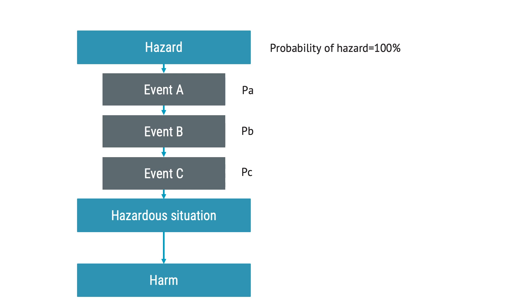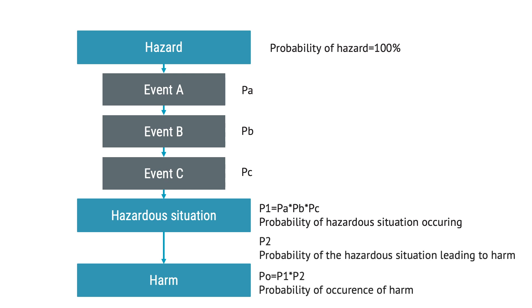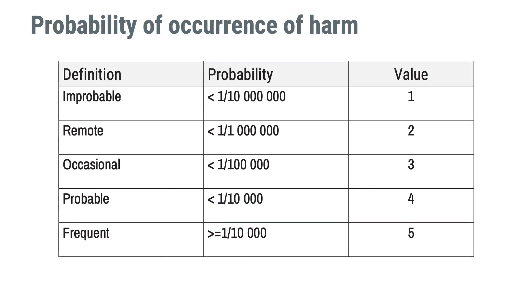These events all need to occur in sequence in order for the hazardous situation to arise. In this case, P1 equals pA times pB times pC. And in order to get to P0 — the probability of occurrence of harm — we need to factor in P2, the probability of the hazardous situation leading to harm, which in the previous example was extremely low. Finally, P0 equals P1 times P2, where P1 is the result of the previous sequences or combinations of events and their respective likelihoods. When you have figured out the probability of occurrence of harm, you can find the right number in your probability of occurrence of harm table and transfer it to your hazard traceability matrix.